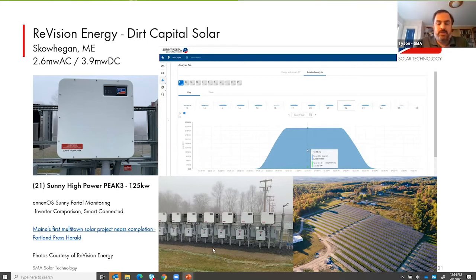Revision has taken advantage of the design concept that Mike introduced, which we're promoting for the Peak 3 on these multi-megawatt ground mount solar farms. This is a centralized architecture where the inverters are co-located together near the point of interconnection and/or transformer pad. If you look at the center photo at the bottom, you'll see the Peak 3 inverters are indeed co-located in a centralized fashion. By doing this, Revision is delivering more of the AC nameplate capacity to the grid with fewer efficiency losses than would be suffered by distributing the inverters throughout the array in a decentralized fashion.